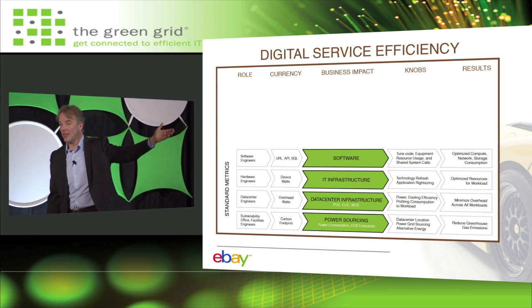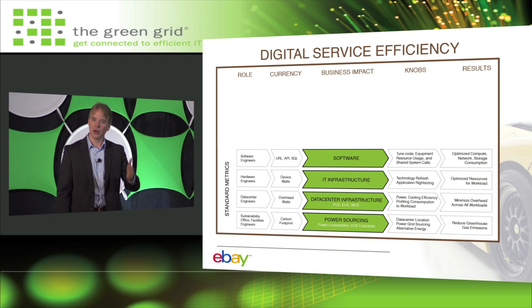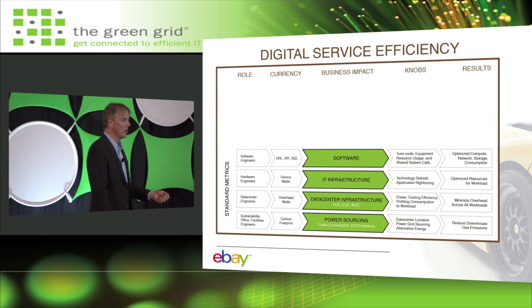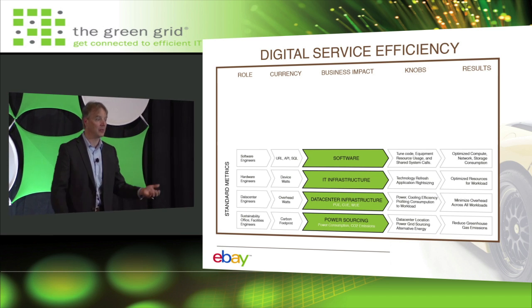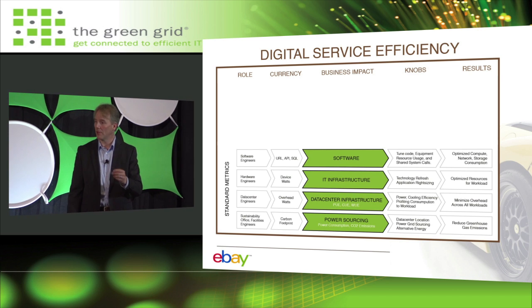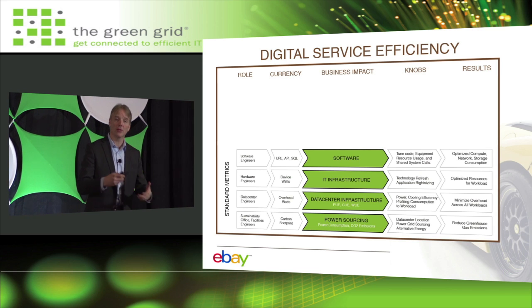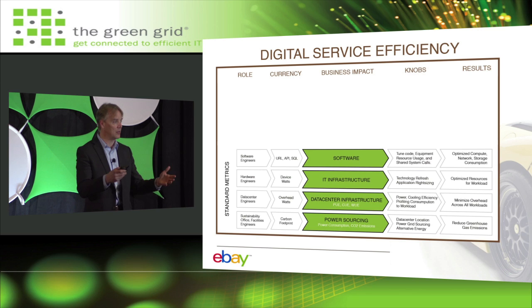So we started doing some right sizing of our applications within our data centers. Okay, work that was happening already. Do we really need Tier 4 for everything? We don't. We found that up to 80% of our applications would work fine in Tier 2 because they can just switch over to another data center without losing data. Why are we building Tier 4 everything? So then we started adjusting that. We're addressing the cost within it, right-sizing the applications to make sure our infrastructure isn't overbuilt and has excessive spend from it.